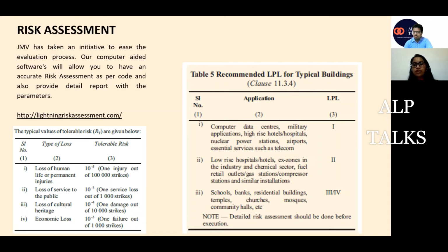Also, there is a chart given in the National Building Code. They have categorized some structures into different levels: computer centers, military applications and high-rise hotels in level 1; low-rise hospitals, hotels, ex-zones, and industries and the chemical sector in level 2; schools, banks and residential buildings in levels 3 and 4. But they have still given a note that a detailed risk assessment should be done before execution. So if I have a residential building, I can go for level 3 or 4, but the risk assessment report is still important before proceeding. Risk assessment plays a very important role in this.